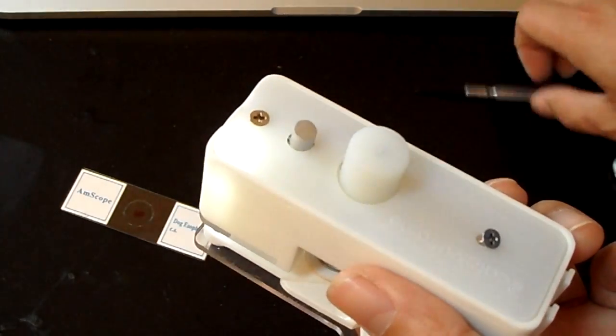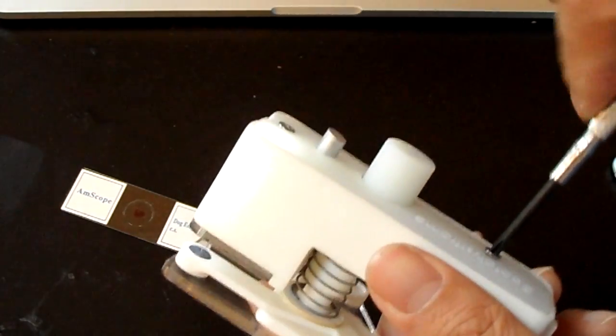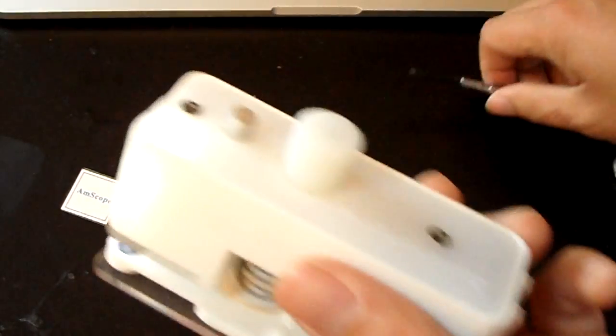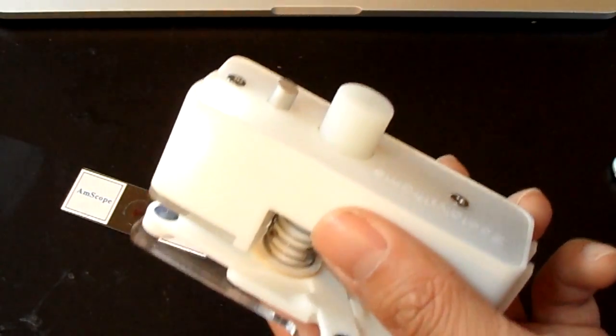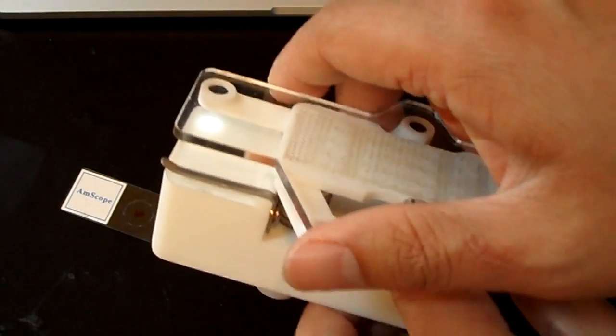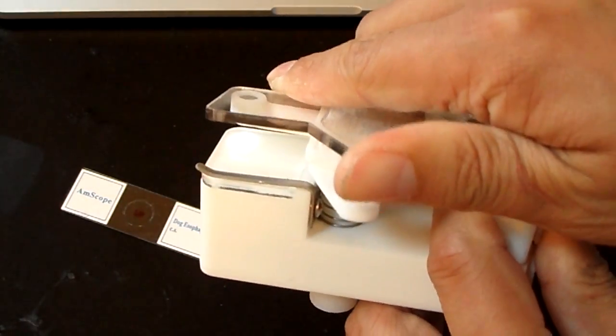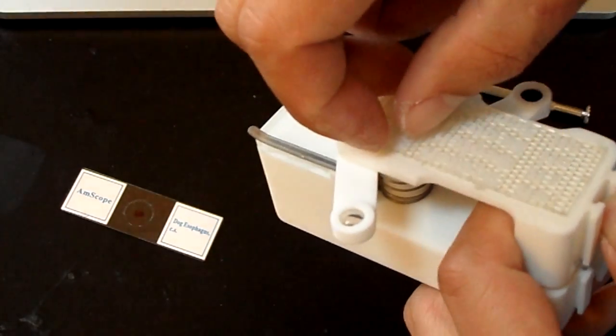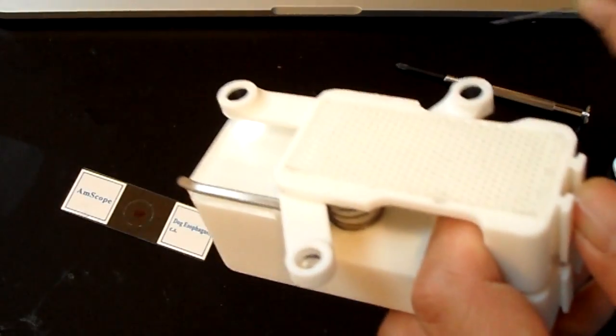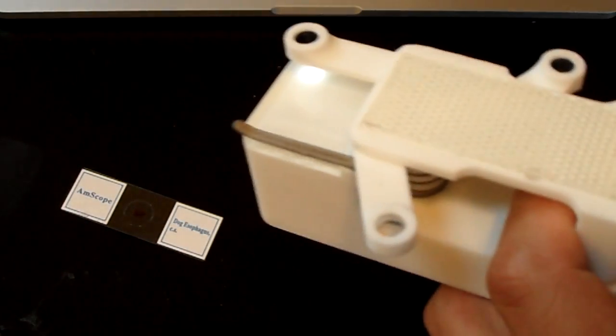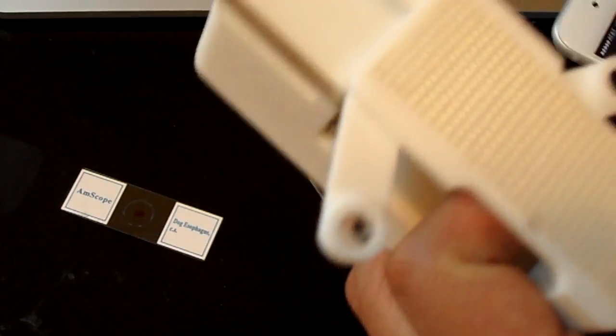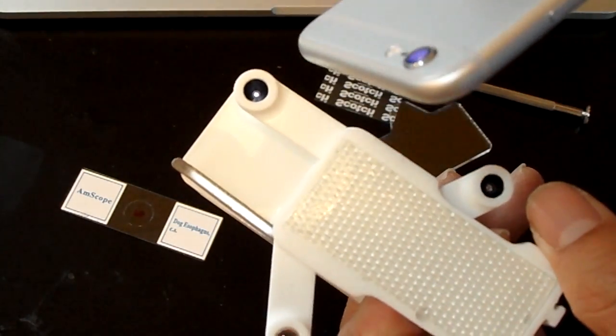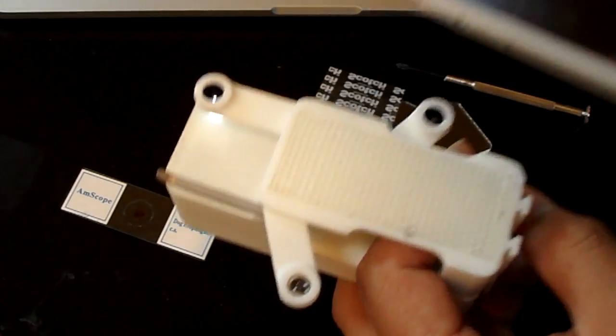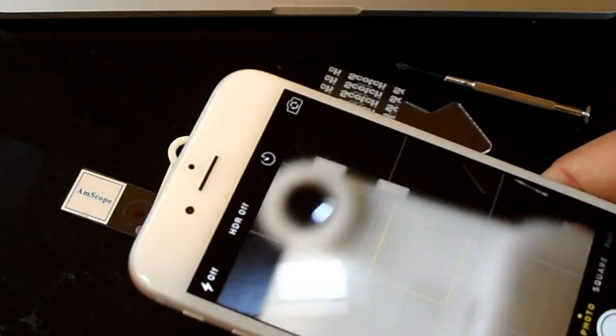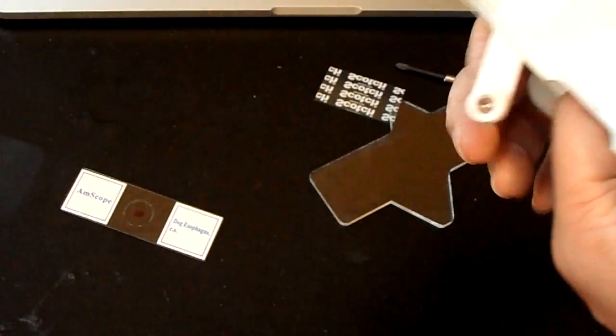And also, when you put in the screws, you don't need to over tighten it because what will happen is the lid will clamp down on the knob and it might make it really hard to turn if you tighten it too much. Okay, the next step is removing the protective acrylic cover piece and removing the plastic film. And when we put this on, we want to have the microscope set to the highest magnification or the smallest lens, so that way we can accurately center it using the grid on the camera app.